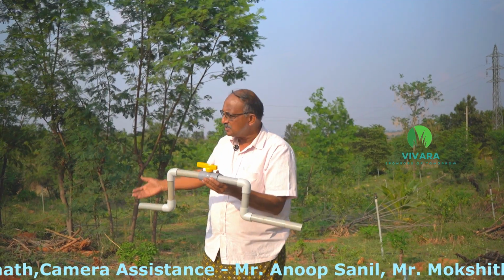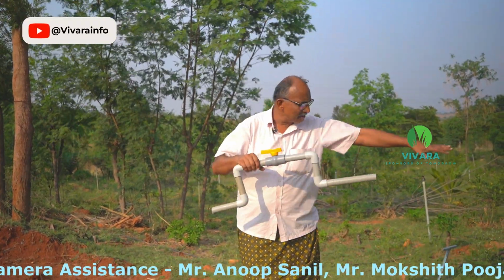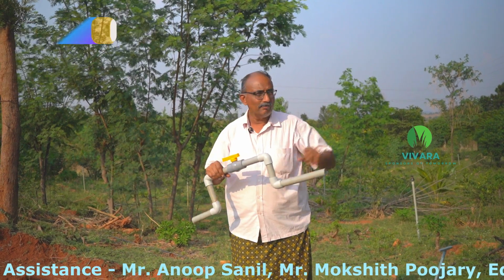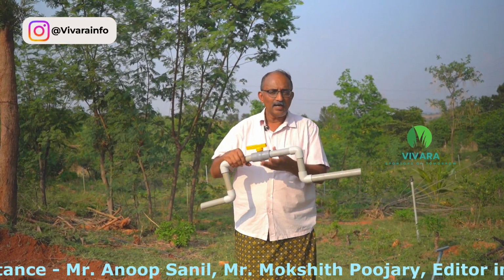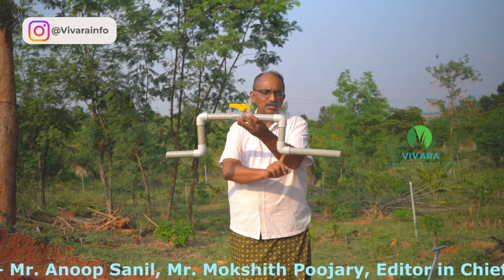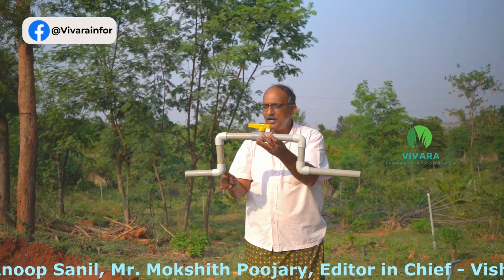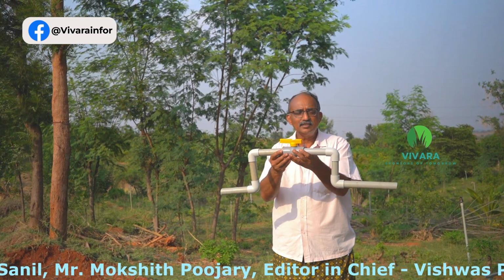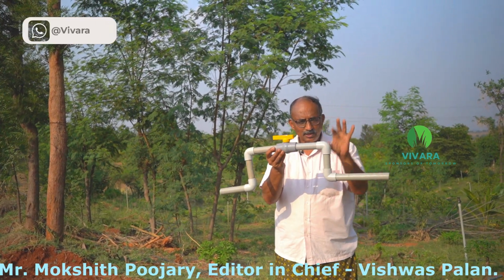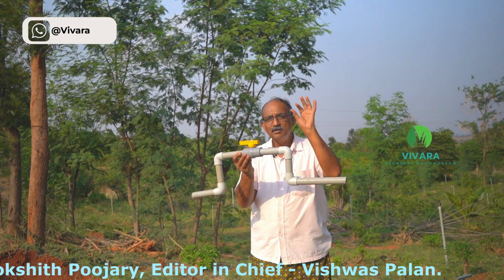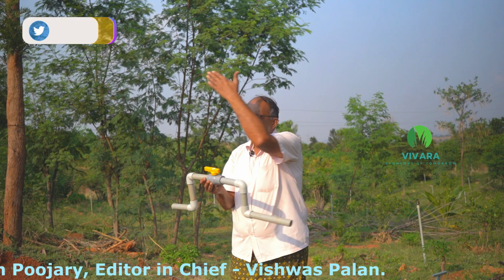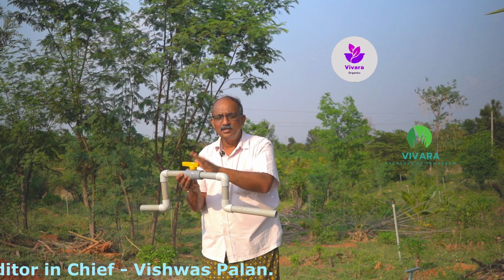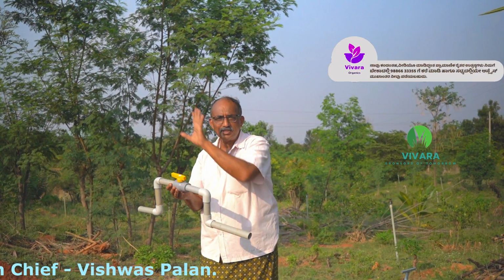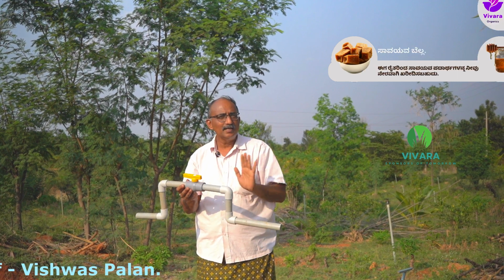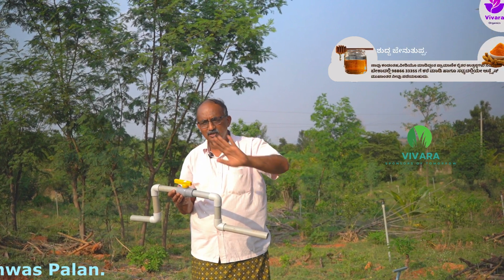Friends, on a typical pipeline system like mine, I have major forking junctions like this, about 8 of them. If I have 8 forking junctions like this and introduce 8 ball control valves, and at each junction I put 4 elbows, I would have introduced 8 fours are 32 elbows. 32 elbows into 3 feet head height is more than 100 feet. My motor specification itself is 100 feet head height. Just by putting 8 valves like this with these elbows, all my motor specification is used up here. It means I am putting unwanted backward pressure onto my motor.